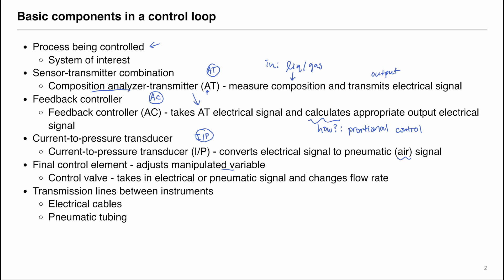Commonly, the final control element could be a control valve. The control valve takes in an electrical or pneumatic signal and changes the flow rate. We also have transmission lines that connect between each instrument. The transmitter sends a signal along a line to the controller AC, which takes in an electrical signal and outputs an electrical signal to the I/P transducer, where it becomes an air signal, and finally feeds into the control valve to control the flow rate.